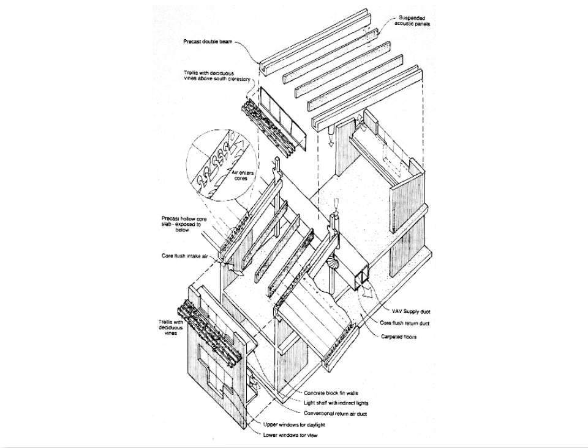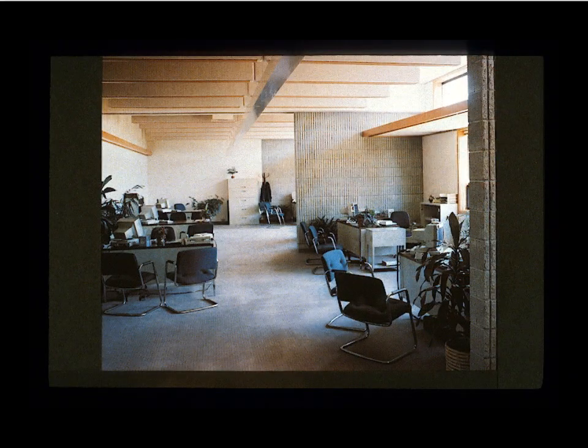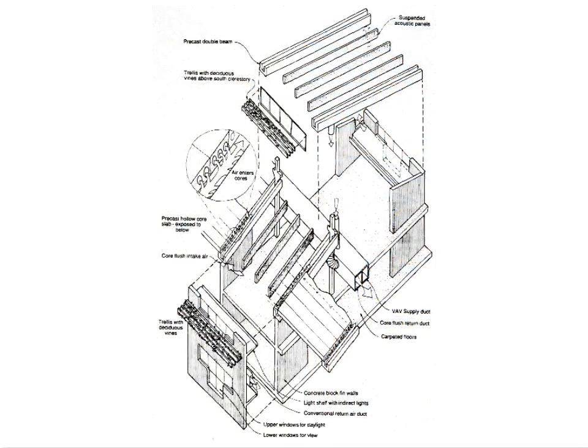So in this case, we're using a hybrid system. It's not completely passive. It's using the mechanical system to distribute air. It's taking in outside air at night in an oversized duct system, dumping that air into the space. The air then moves around inside the space where it can contact any exposed mass surfaces. In this case, the ceiling mass is exposed and the vertical wall structural mass is exposed. So that can be cooled down. Then it's sort of sucked up into an intake through a kind of U-shaped precast concrete channel.